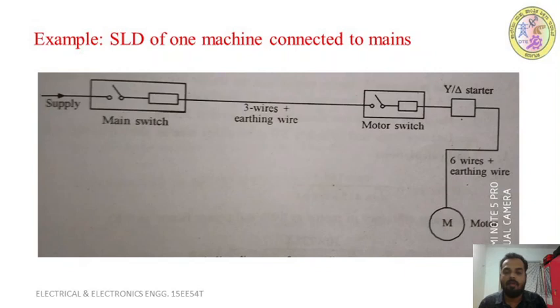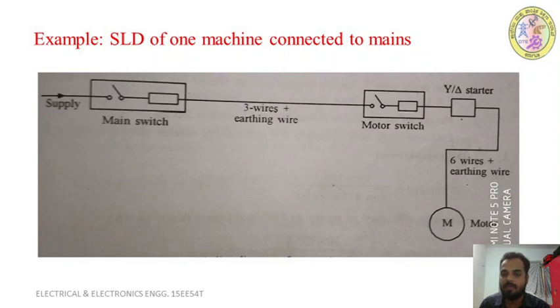This is the single line diagram of a pump set connected to the mains. From the supply, it goes to the main switchboard, which has an ICTP and a fuse unit. From there it goes to the starter board, where we take three wires plus an earth wire. In the starter board, there is again an ICTP, a fuse, and a starter. Since the motor rating is above 1 HP, we use a star-delta starter, and from the starter we take six wires plus an earth wire to the motor terminals. The pump is mounted on a foundation.